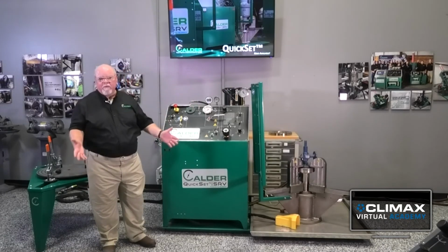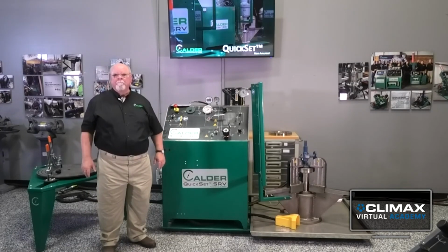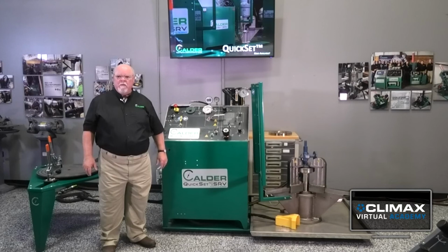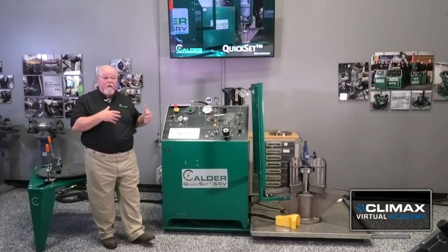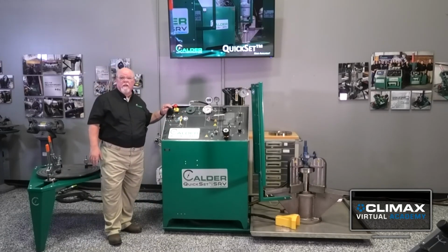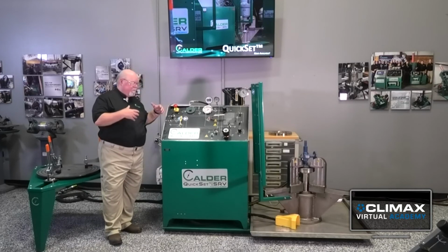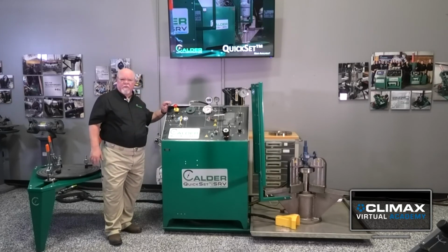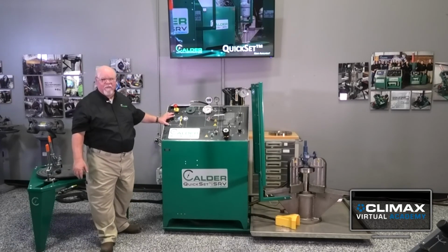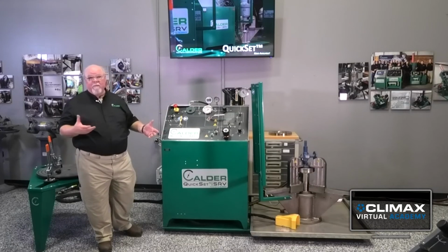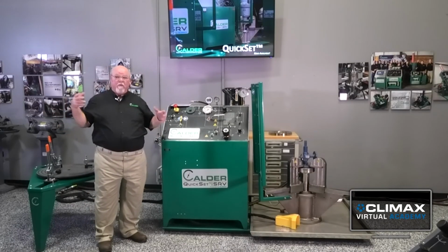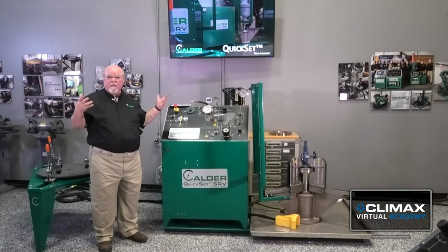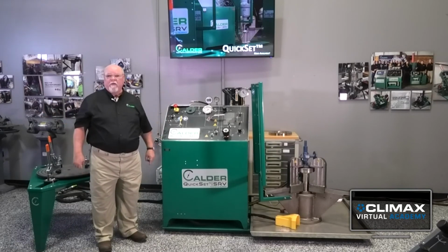Good question. Can I purchase separately and use the Calder testing software and bubble counter on my old testing? The data acquisition system is independent of the unit that it's applied to. In this particular case, we've packaged it so that it bolts onto the cabinet inside. We have other options that would be a better suit for that, but yes, you could take the unit used for this machine and use it on others as well. If you have transducers, you can place a transducer external to the machine and attach it right to the same data acquisition system. Good question.